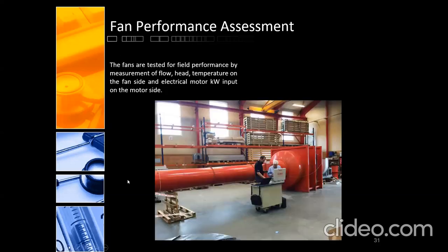Next, fan performance assessment. Ito na. Mga pang test ng fan. So, the fans are tested for field performance by measurement of flow, head, temperature on the fan side, and electrical motor kilowatt on the motor side.